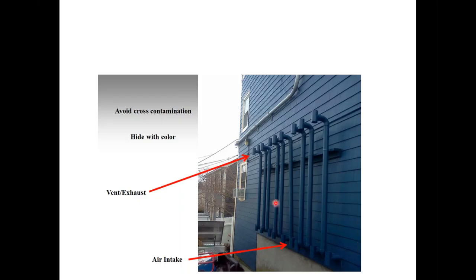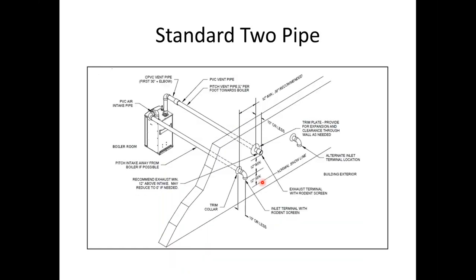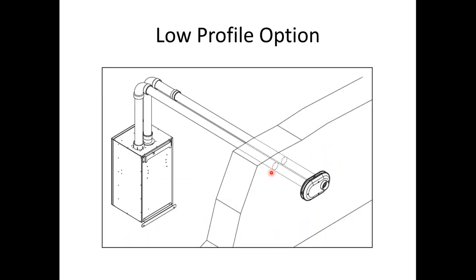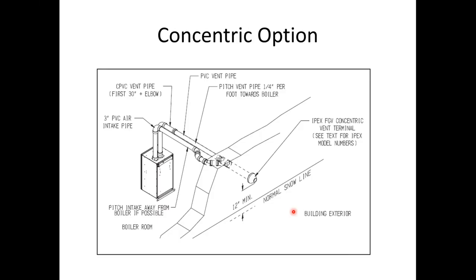This is a building downtown, showing all the boilers installed and multiply piped. Oh, excuse me. Our standard 2-pipe venting, just need to have them 12 inches apart from center to center is the minimum, and 12 inches above the normal snow line. Showing the low profile option or the concentric option.